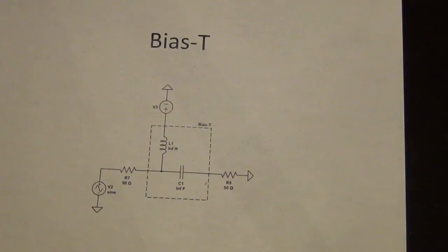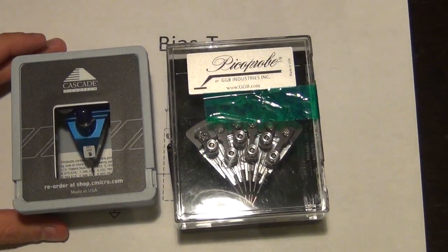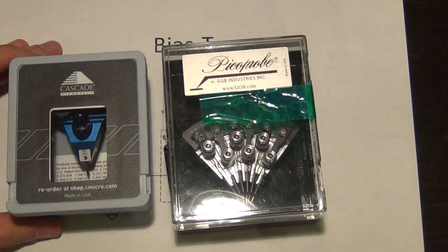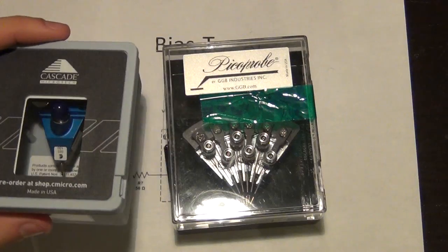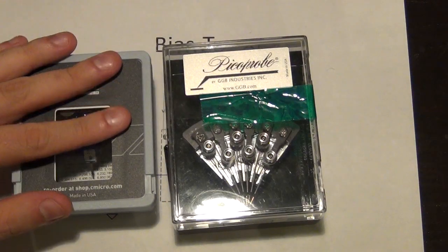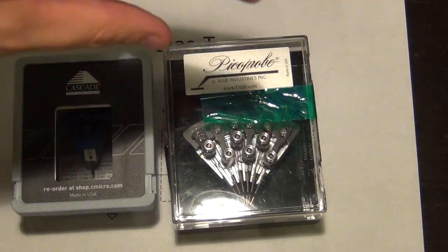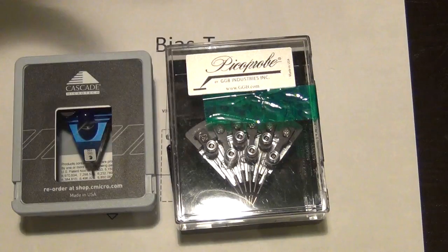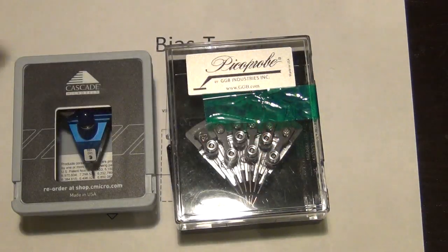So as the last thing I wanted to show you is probes. These guys are probably the things that fall victim the most during measurements. They are extremely expensive. This is a 67 gigahertz GSG probe. I'll show you what that means. And these guys can cost several $1,000s, I think $4,000 or $5,000 for something like this. And if you make a custom-made one like this one, you're talking about $10,000 to $15,000. So you have to be extremely careful with these.